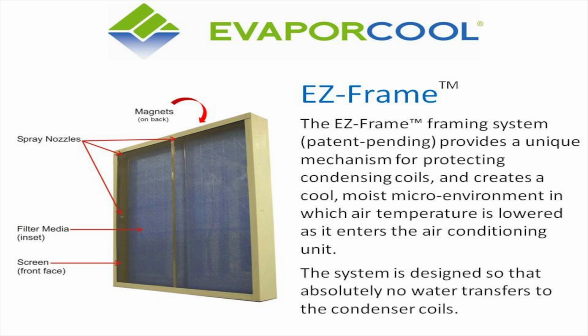And then the third part is the frame itself, and I'll show you pictures of what it looks like. The frame attaches onto the outside of the coil area of the unit, and that frame has three parts to it. It has the nozzles where the water is being sprayed. It's got a filter media, and it's got a screen, and that's attached, and all this is attached through magnets.